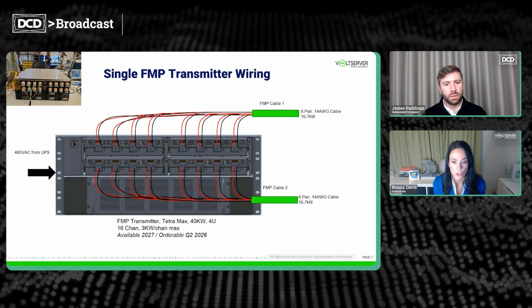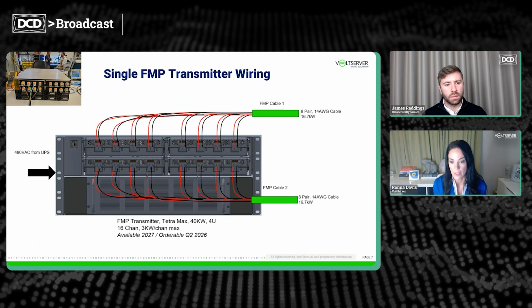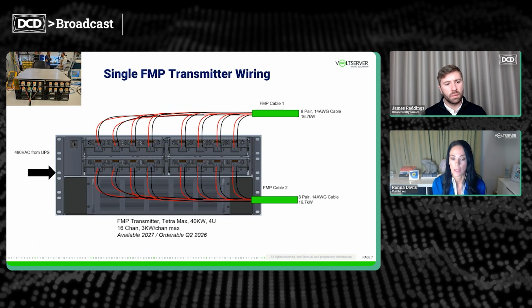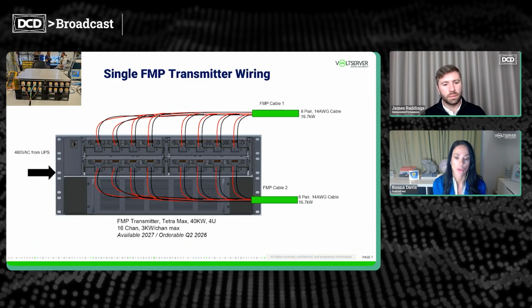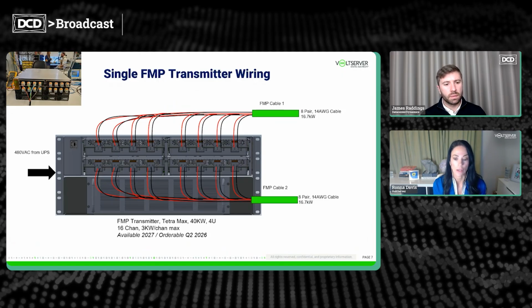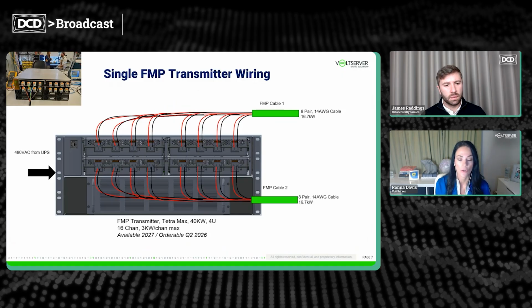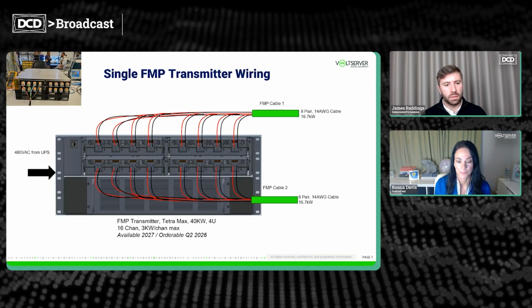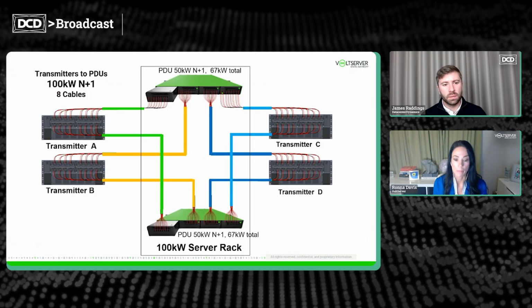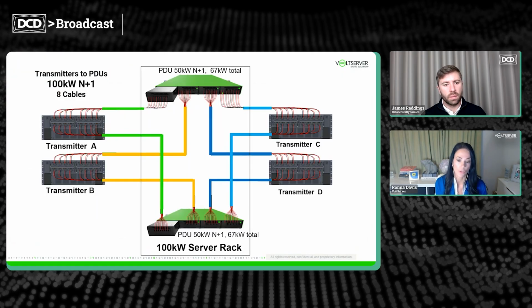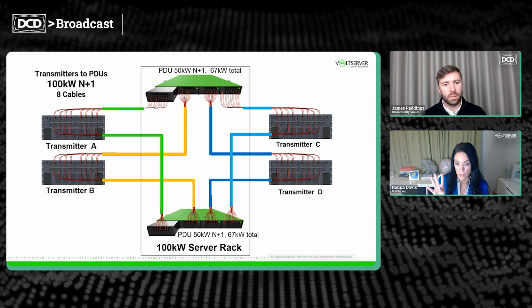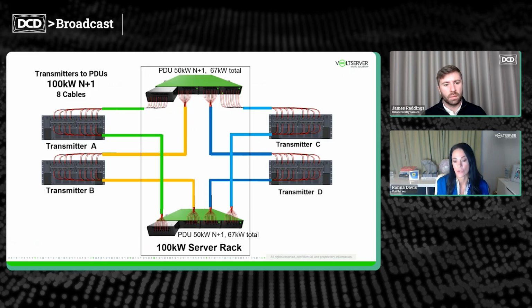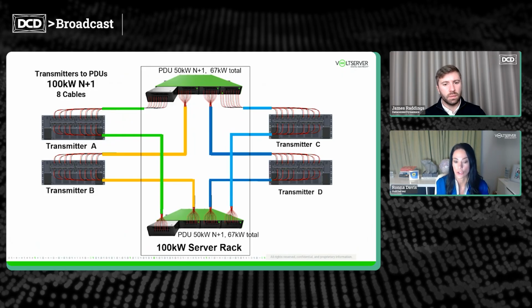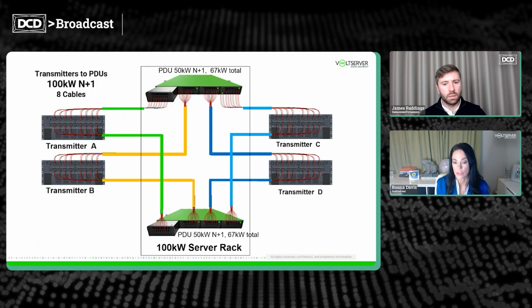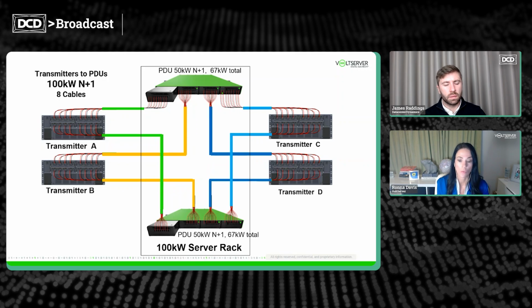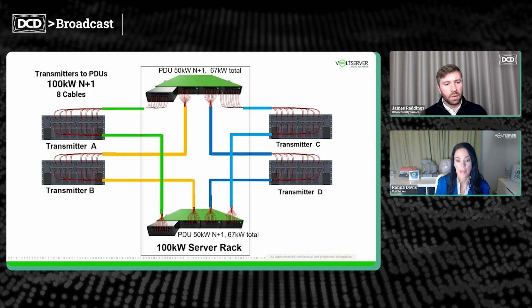Let's take a closer look at the transmitters and what the wiring looks like on a transmitter. I'm showing you our 40 kilowatt transmitter. It has 16 3 kilowatt channels. We're using 2 8-pair cables for each 40 kilowatt transmitter. So you remember that the 350 volt high voltage DC server PDU has 4 power sleds, right? Well, this diagram demonstrates how you can achieve an N+1 architecture sourcing from 4 unique transmitters for a 100 kilowatt N+1 in only 2 rack units at the server cabinet.